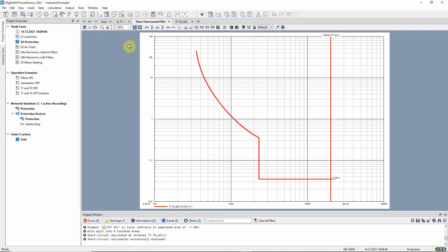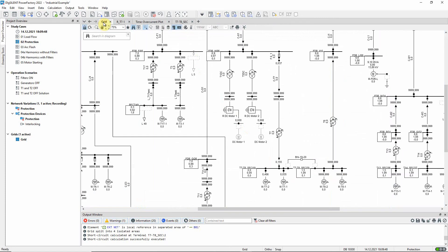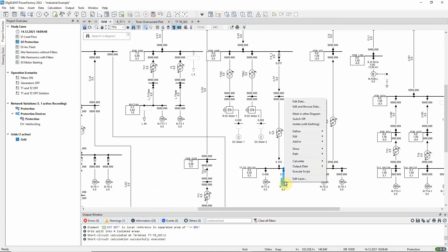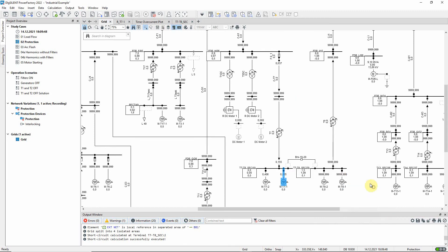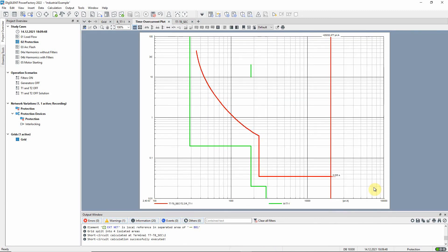On time over current plots it is possible to represent not only the characteristics of protection devices but also the characteristics of the protected elements. Let us add the characteristic of the asynchronous machine. As you can see, in this case there is a starting current that is approximately six times higher than the nominal current. This has to be taken into account when selecting relay settings.